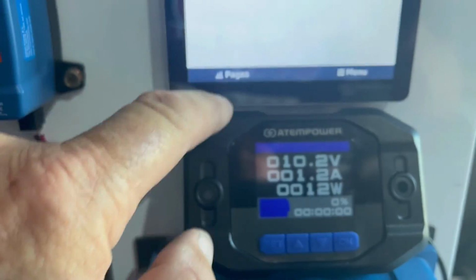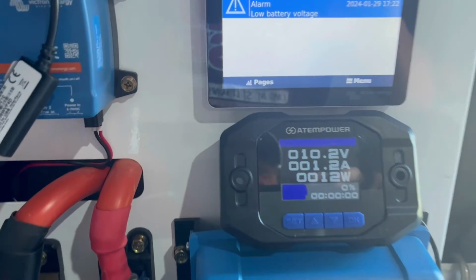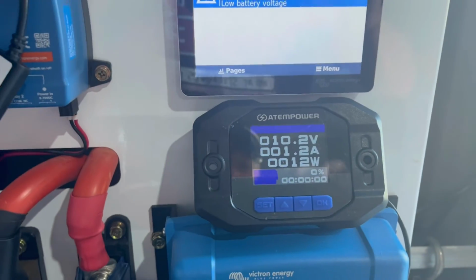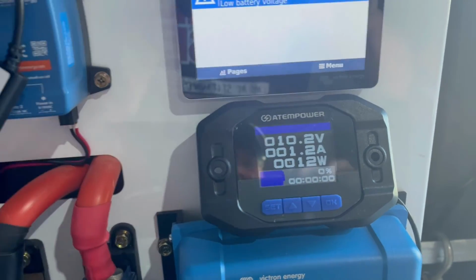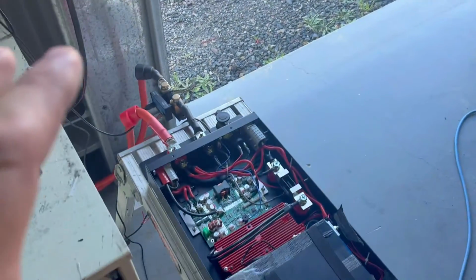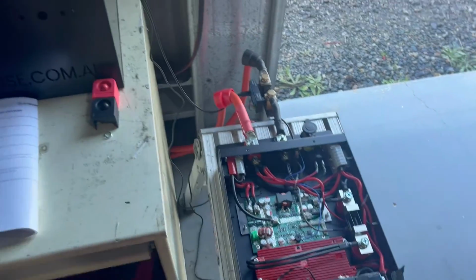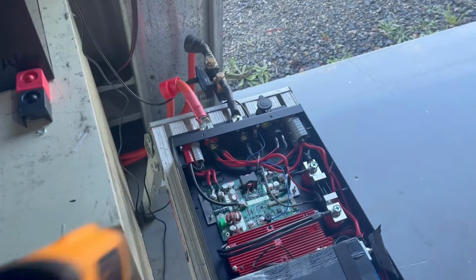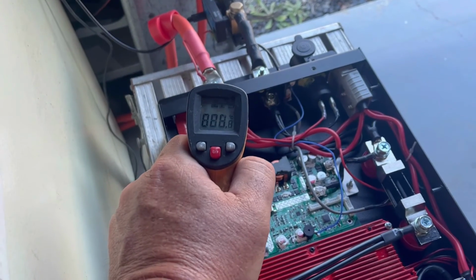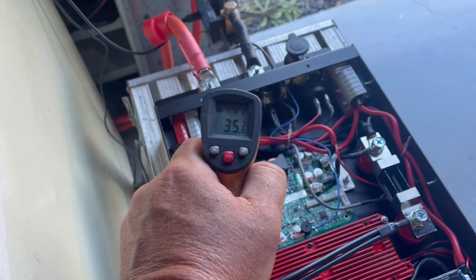And it was a lot lower than 10 volts, and we even saw it on there. So I don't like that, but it's no worse than a lot of other batteries. So it made its rated capacity, that's a pass. The terminals, they didn't really heat up, and yep, happy to eat my words on that one.